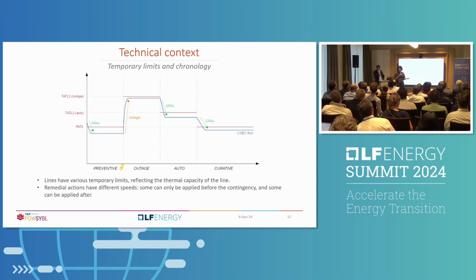So as I said, the lines have limits because of the heat that's produced in the line, and the heat isn't produced instantly. The line doesn't go suddenly from, I don't know, 50 degrees Celsius to 80 degrees Celsius instantly. This means that if a line is overloaded, it can be overloaded for a certain time period before it becomes too hot. So this is kind of represented through this graph. Initially, you have what we call the permanent limit. This is the limit which the line, the amount of megawatts that the line can transfer forever without causing an issue.